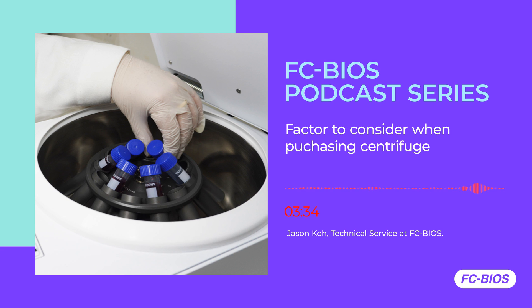The safety features of a centrifuge are also critical. The wrong operating procedure of a centrifuge can pose very serious safety issues — you can be exposed to physical hazards due to mechanical failure, or even biological hazards. To avoid such incidents, consider features like the electrical lid lock, which prevents the lid from being opened accidentally while the centrifuge is running. Some centrifuges also come with a biohazard seal, which prevents leakage from biohazard materials, and rotor recognition technology, which senses the rotor being installed and ensures it does not surpass the maximum speed allowed.